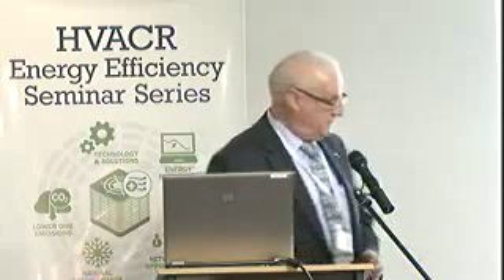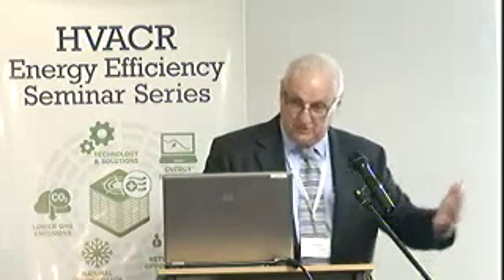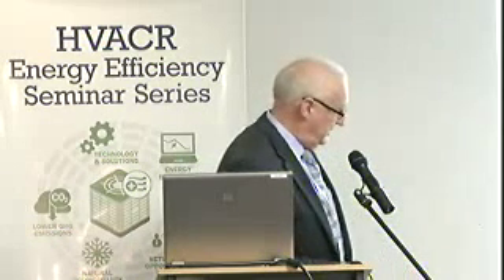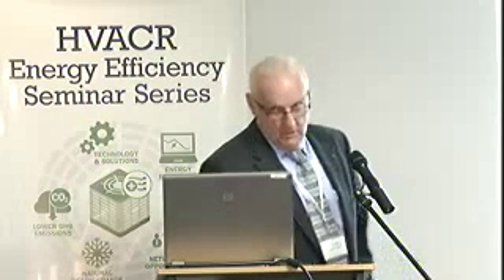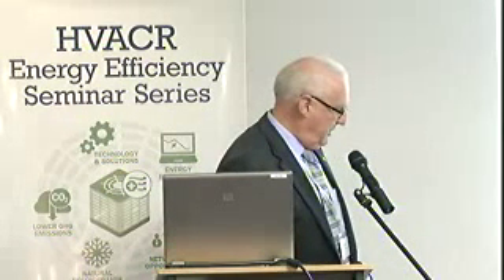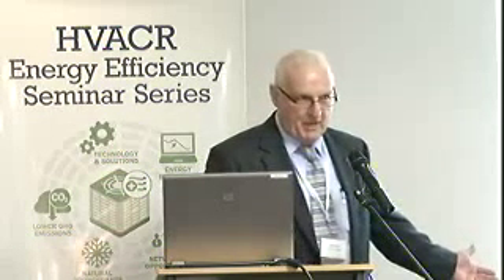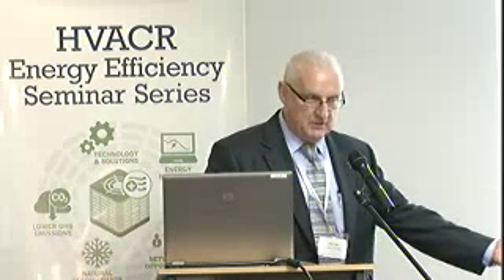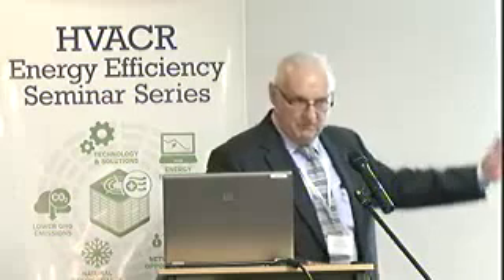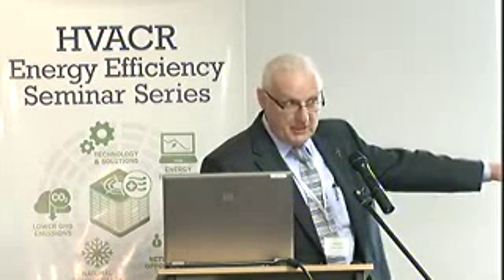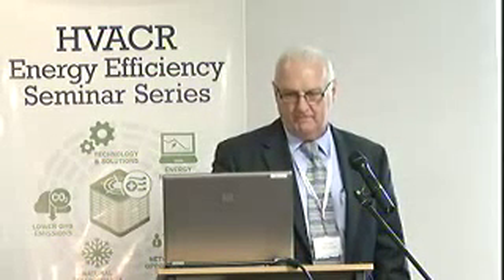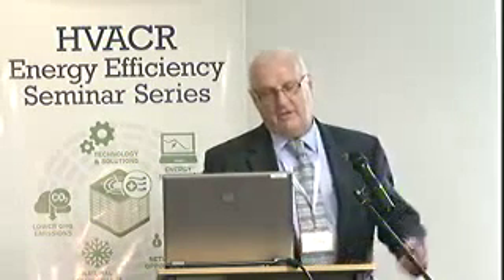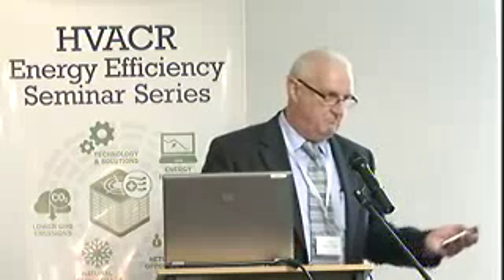So really this is a restatement of the same thing, but when we go to a site to do a site survey, one of the things we also like to find out is if there's been an energy audit, what's the split up of the loads? If not, we have to work that out for ourselves when we're there, so that we can then apply it. Here we're showing refrigeration of 52% in a particular supermarket, so we'd go 52% of the kilowatt hours times, let's say we're getting a 10% reduction in voltage. Before you saw on the slide it's about a 15% reduction in energy for the refrigeration motor, so it'd be 15% of 52% of the total kilowatt hours for the site, just as one example of the process we go through for calculating what energy savings might be. Again, with refrigeration, I know that's not the whole game here today. We're also talking about air conditioning, somewhat similar systems.